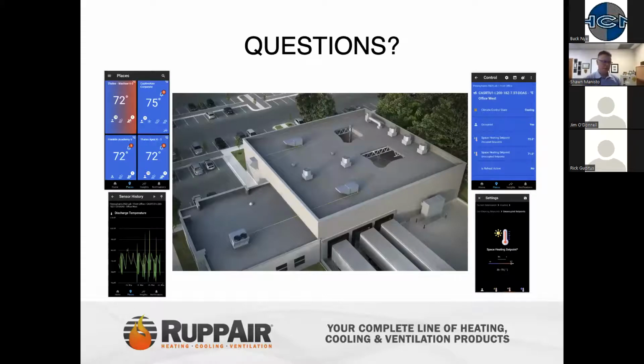So not having the visualization of the exact application they are in, but number one, having return air capability will catch a lot of that heat at the top deck. Having those exhaust fans or barometric pressure in place elsewhere in the building will help move that heat across the building. So returns, having the exhaust in place, and then third would be the implementation of HVLS. Okay, the large fans to help push the air down.